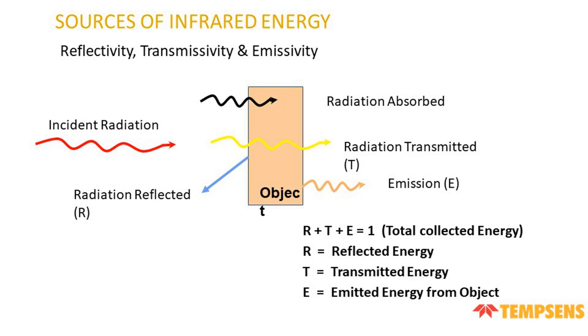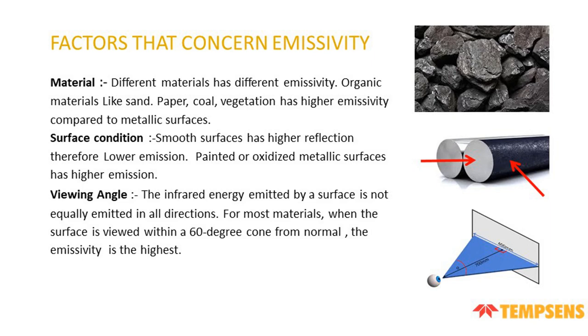Source of infrared energy: reflectivity, transmissivity, and emissivity. Factors concerning the emissivity. Material: different materials have different emissivity. Organic material like sand, paper, coal, vegetation has high emissivity compared to metallic surface. Surface condition: a smooth surface has higher reflection, therefore lower emissivity. Painted and oxidized material surface has high emissivity. Viewing angle: the infrared energy emitted by the surface is not equal in all directions. For most materials, when the surface is viewed within a 60-degree cone from the normal, the emissivity is highest.